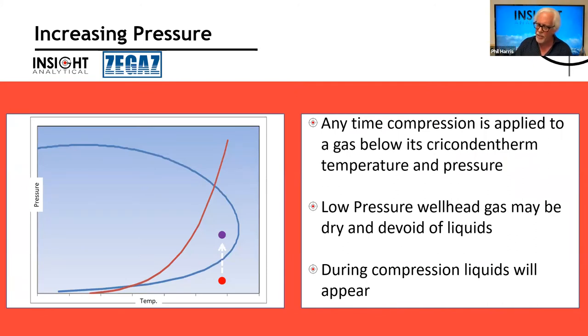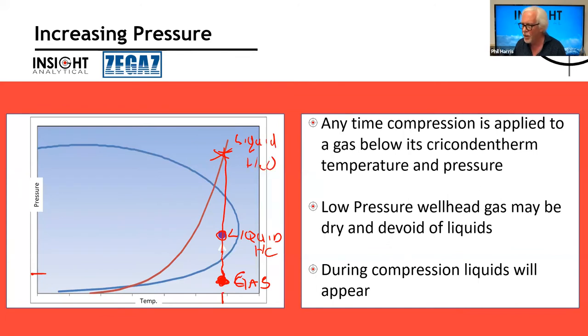So if we have this hypothetical phase diagram here for hydrocarbons and a water dew point curve, and our process fluid is at this temperature and pressure, whatever those numbers correspond to over here, it's all a gas. As we increase the pressure, we risk hitting the edge of this phase envelope, and as soon as we cross it, now we've got liquid hydrocarbons. And if we increase the pressure on this stream again and got up to here, we'd have liquid water. So increasing the pressure is one of the ways that we end up hitting a hydrocarbon or a water dew point in a stream that previously was all gas phase.